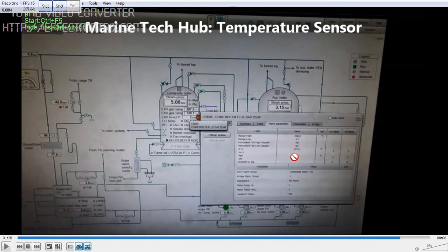Do not change the alarm settings any of this. So very important and test these alarms. Very important. Sometimes if you are testing alarms and you forget to put the value here, then you will not get any alarm. So always make sure that whenever you test alarm by simulating the system, put back the limit so that you are safe. If you have any message regarding this, please let me know. Thank you.